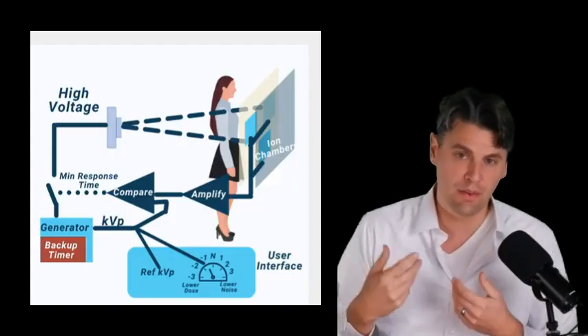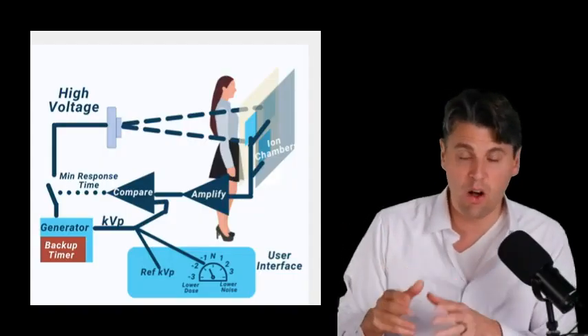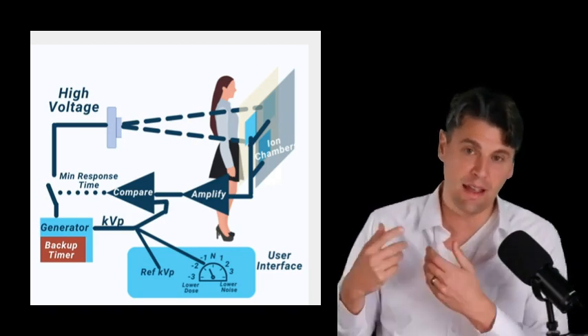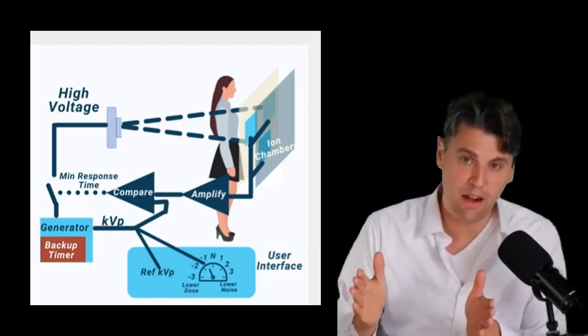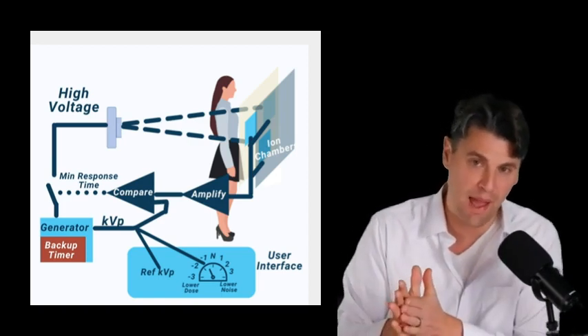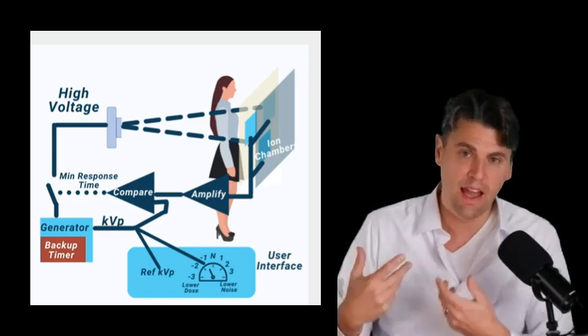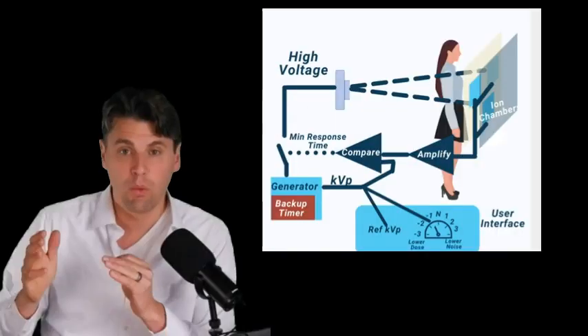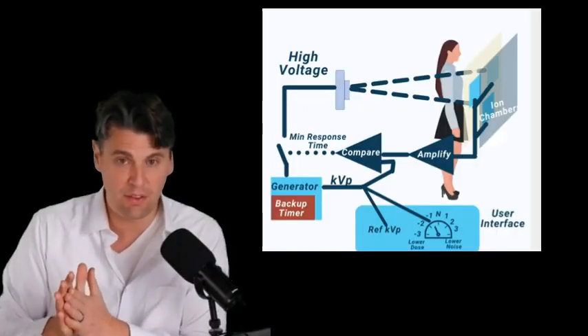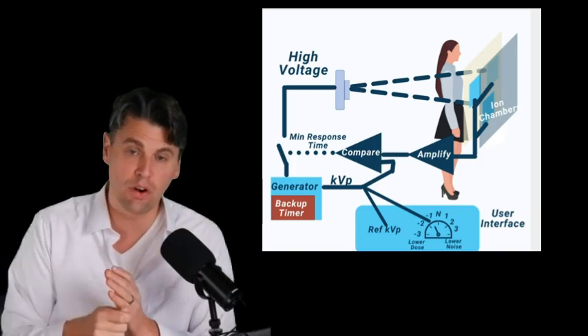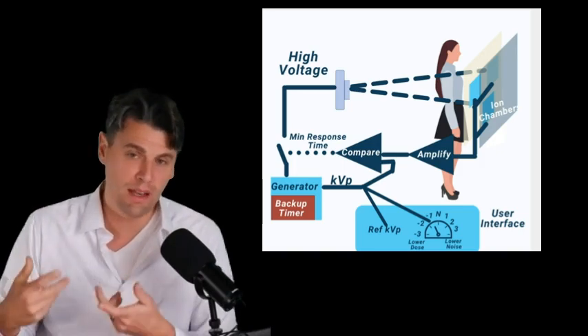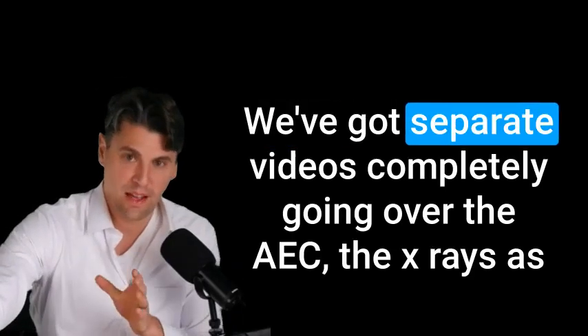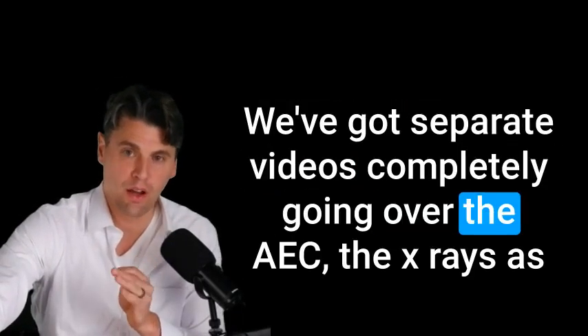Alternatively, the systems now have ways that we call automated exposure control. And this automated exposure control actually takes a measurement during the acquisition to see how many x-rays have actually passed through the patient, and thus how good a quality of the x-ray image we're going to have at that given time. Once there's enough x-rays that have passed through, then the automated exposure control says turn off the acquisition. So automated exposure control just sets the duration of your x-ray acquisition. We've got separate videos completely going over the AEC.